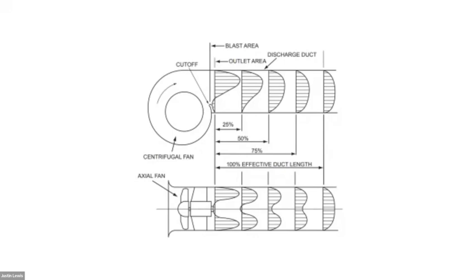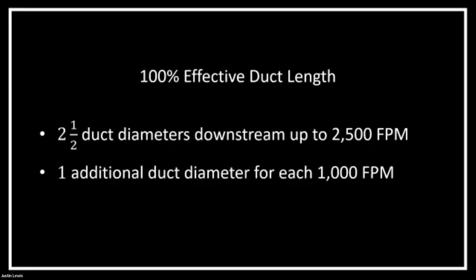So look at this AMCA diagram. This outlines the effective duct length required for proper airflow development. So if we look at that, for proper airflow development, we need 2.5 duct diameters downstream of a fan for a system operating at 2,500 feet per minute. An additional duct diameter needs to be added for every added 1,000 feet per minute. This is just for proper development of stable airflow.